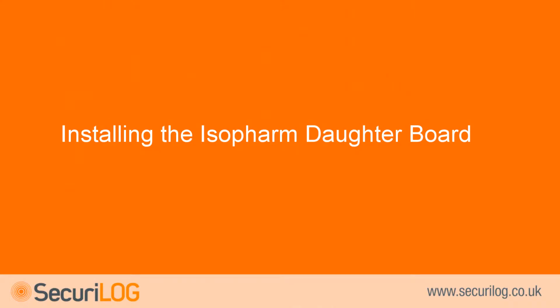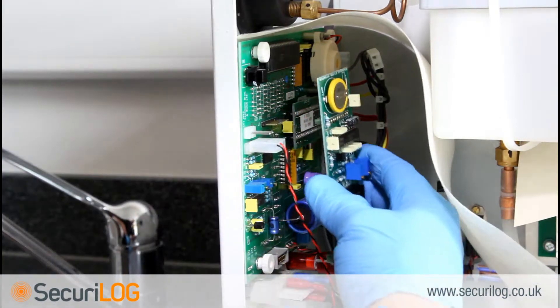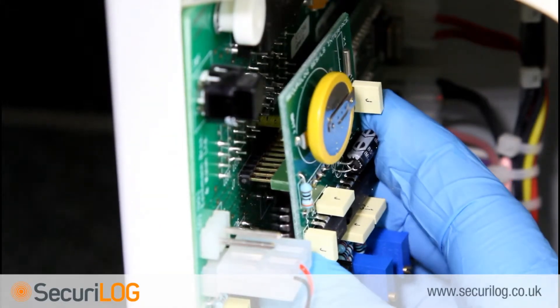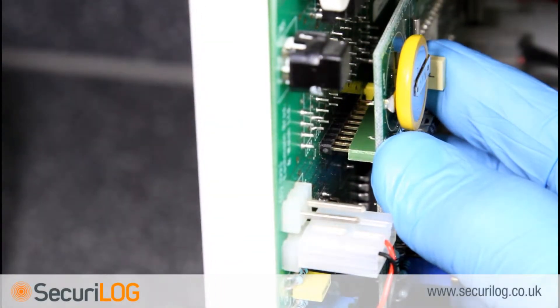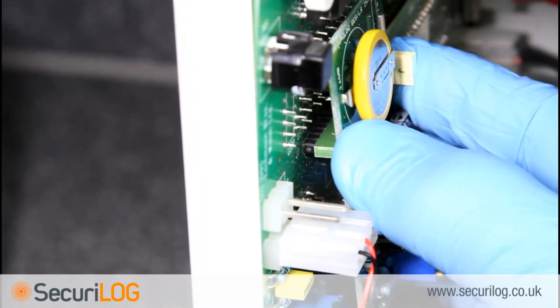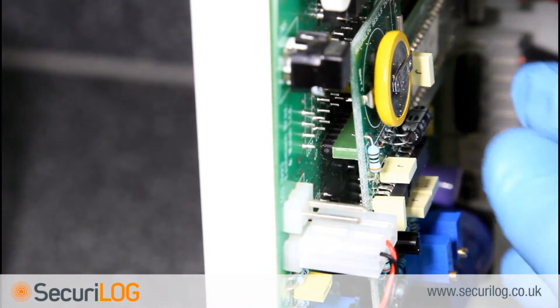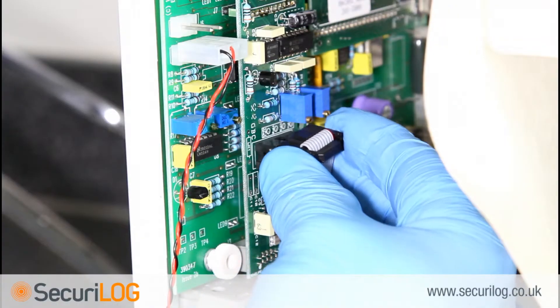Installing the Isopharm daughterboard: this part of the installation is only required if the steriliser does not already have a daughterboard installed. Fit the Isopharm daughterboard onto the main PCB. Take care to ensure that the 10-pin connector at the top is connected to all 10 pins on the main board, as this is easily misplaced. Once inserted, plug in the Securilog ribbon cable.